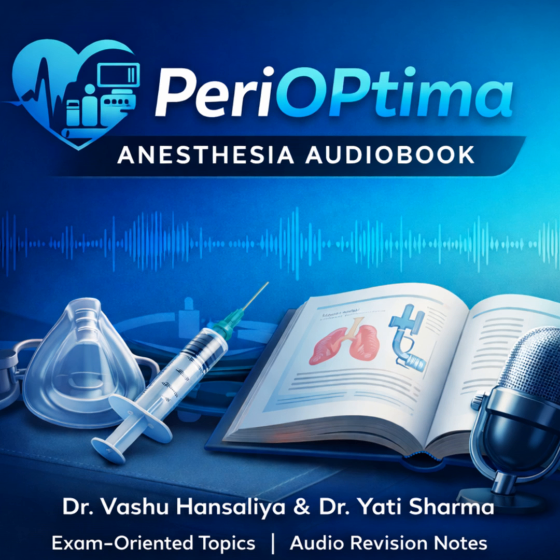Okay, which brings us to the intermediate pressure system. This is the bridge. It starts immediately after that first pressure regulator. The regulator steps that terrifying 2,000 psi down to a much more manageable, stable working pressure. How much are we talking? Usually around 45 to 60 psi, roughly 3 to 4 bar. This system includes the pipeline inlets coming from the wall, which also arrive at this pressure, and the plumbing for the oxygen flush valve. It runs all the way up to the flow control valves.